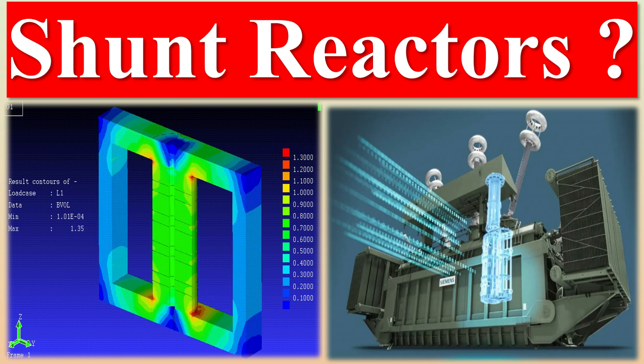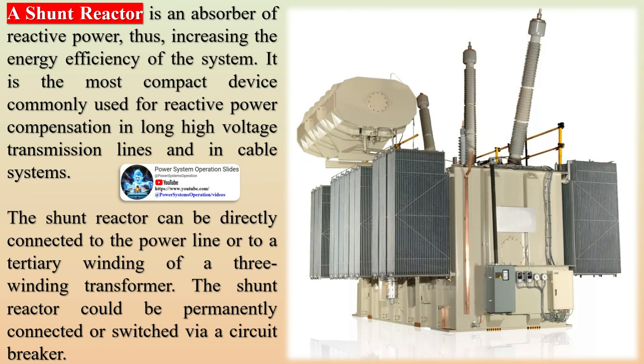A shunt reactor is an absorber of reactive power, thus increasing the energy efficiency of the system. It is the most compact device commonly used for reactive power compensation in long high-voltage transmission lines and in cable systems. The shunt reactor can be directly connected to the power line or to a tertiary winding of a three-winding transformer.